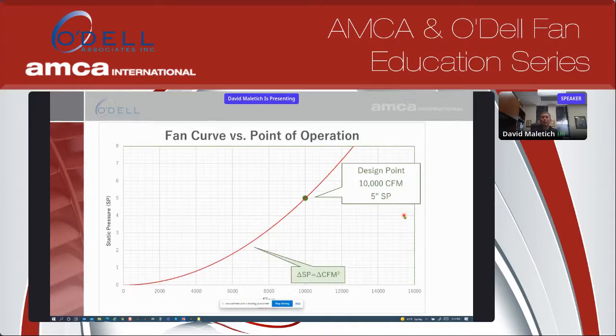And that system curve has an infinite number of points on it. It's simple to go back again to Bill Howarth when he did the fan laws. The second fan law was pressure varies by the square of the change in flow. In this case, the system operates very similarly, in that pressure varies by the square of the change in flow. And within a given system, what I mean by a given system is we don't add branches, filters don't get clogged, we don't open up registers. Within a system, if you increase flow, pressure goes up; decrease flow, pressure goes down.